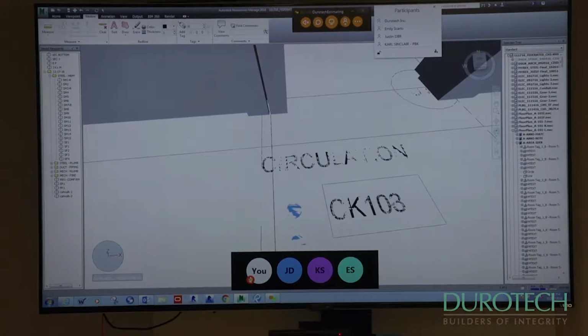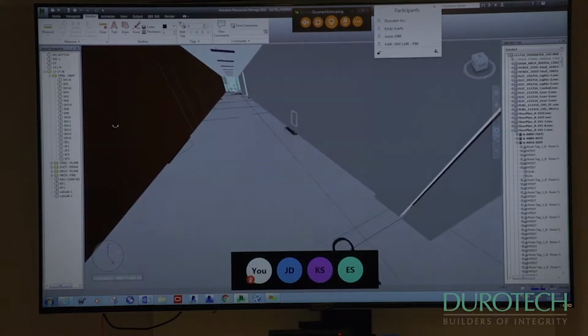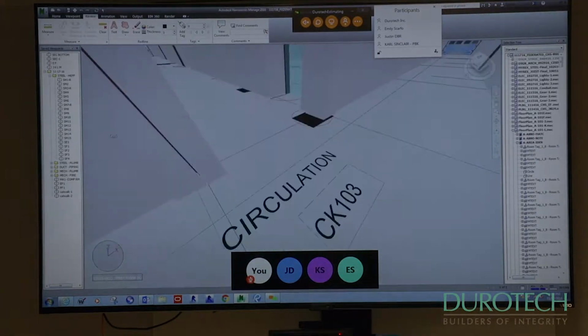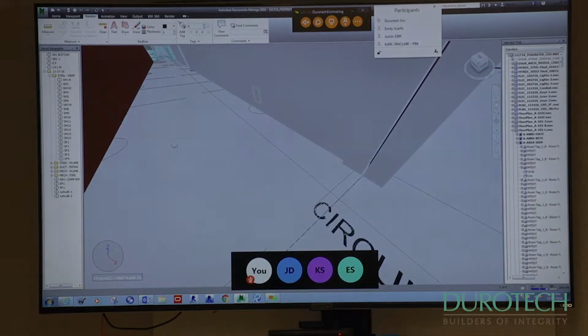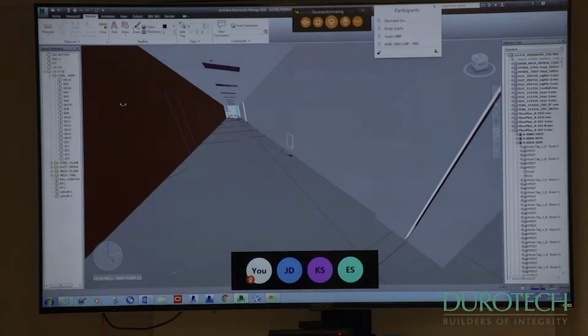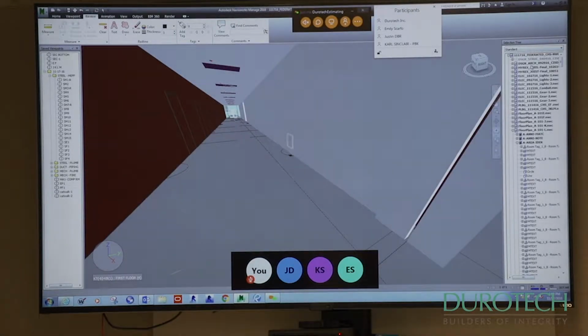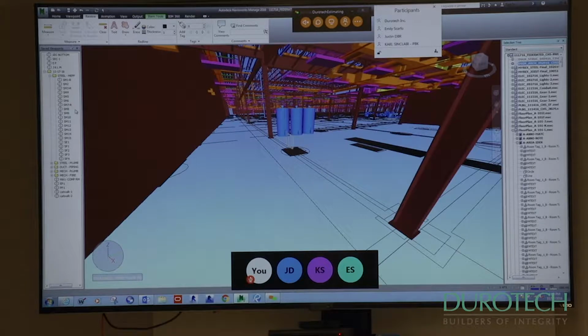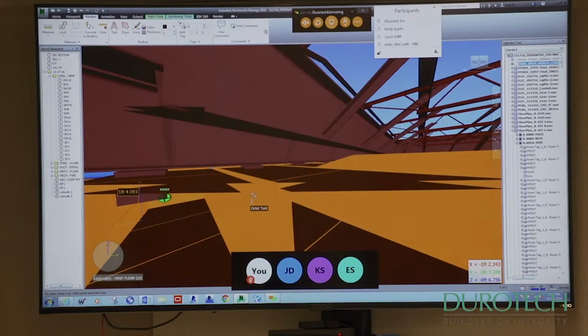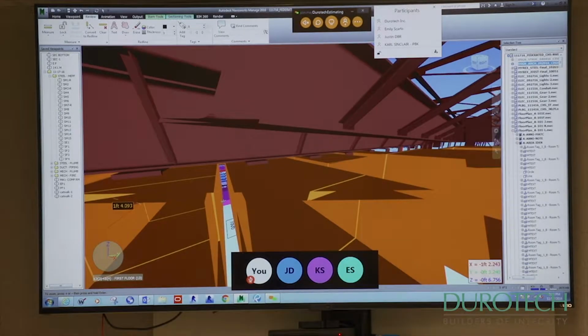So this is where we kind of go back to some of the issues that I know we ran into in areas A, B, C, and D, or going down that corridor, which right now it's comfortably at 10, and to push it at maybe 9 feet, then you can see what my concern is now. That becomes a 9 feet shallow corridor that runs all the way down to the point of exit. Is there any scope for you to widen up the ducts?